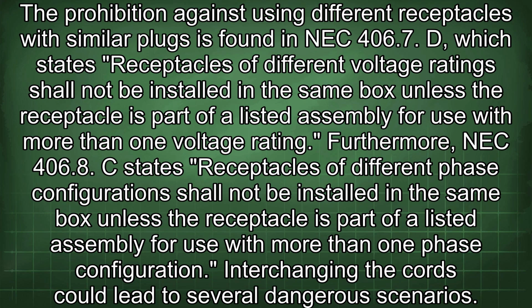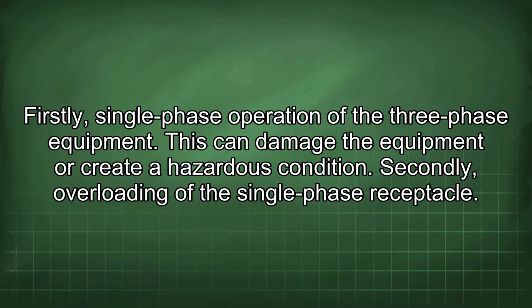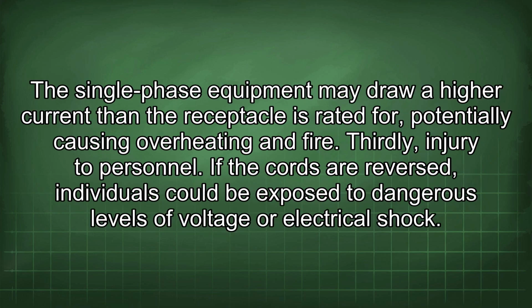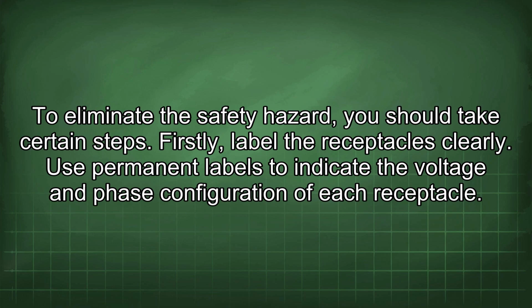Interchanging the cords could lead to several dangerous scenarios. Firstly, single-phase operation of the three-phase equipment. This can damage the equipment or create a hazardous condition. Secondly, overloading of the single-phase receptacle. The single-phase equipment may draw a higher current than the receptacle is rated for, potentially causing overheating and fire. Thirdly, injury to personnel. If the cords are reversed, individuals could be exposed to dangerous levels of voltage or electrical shock.